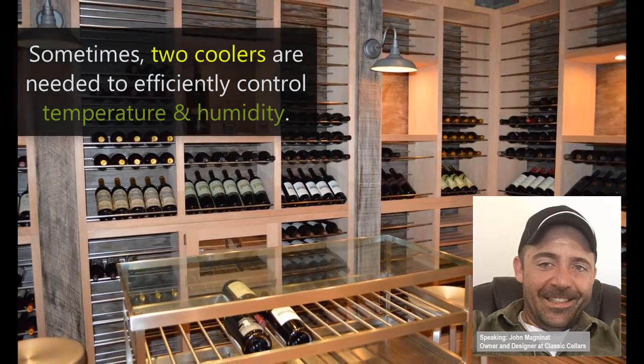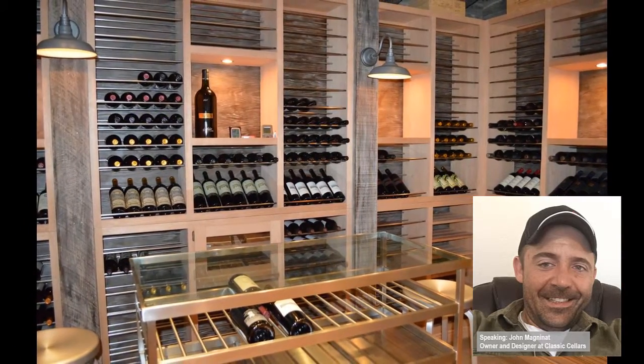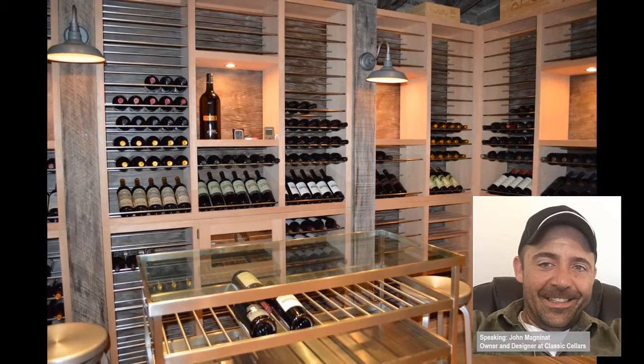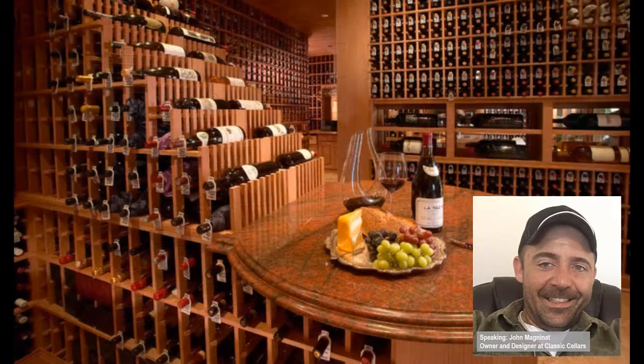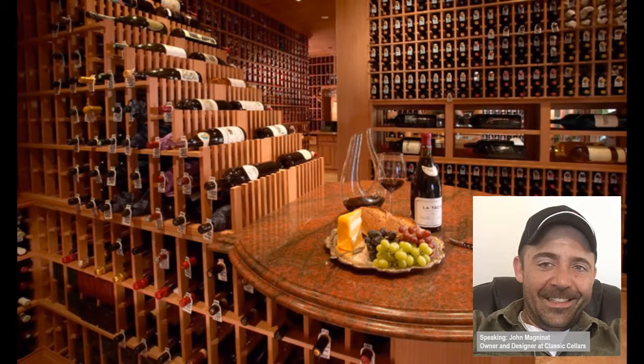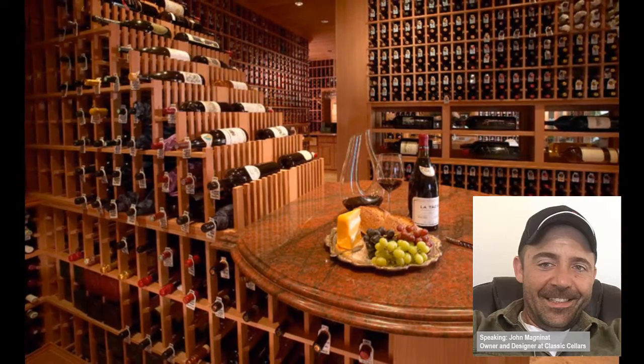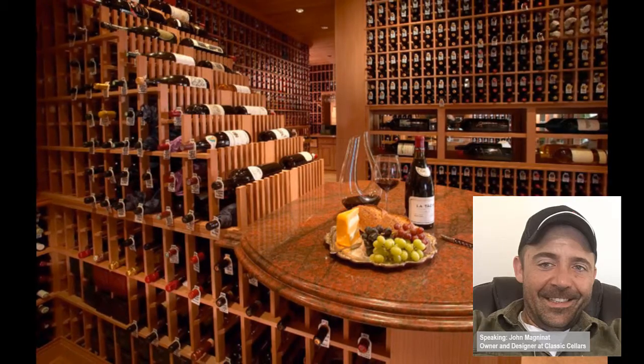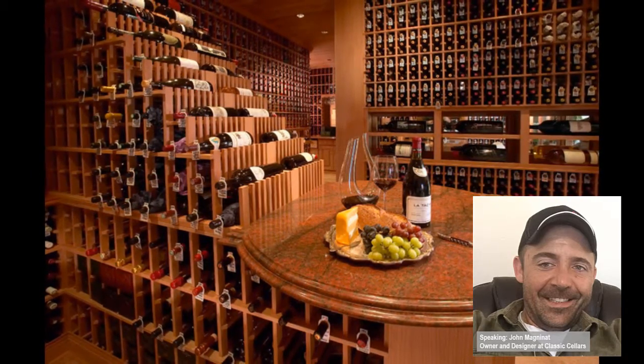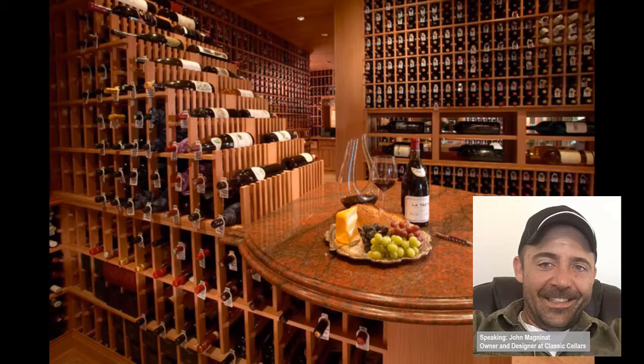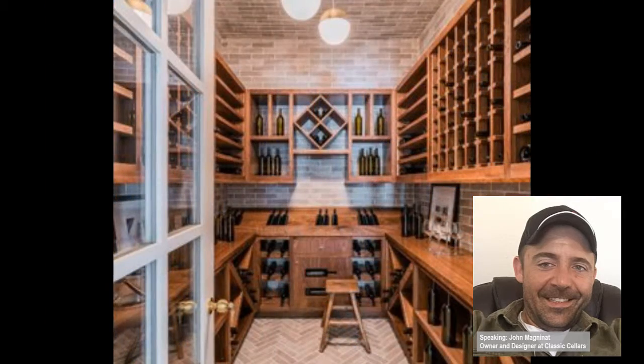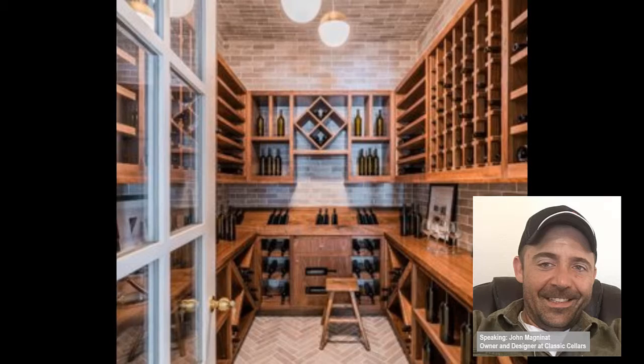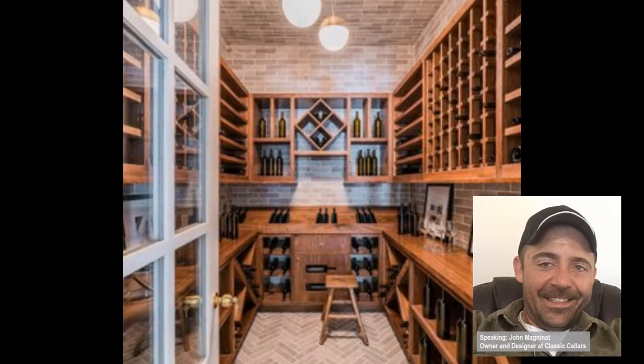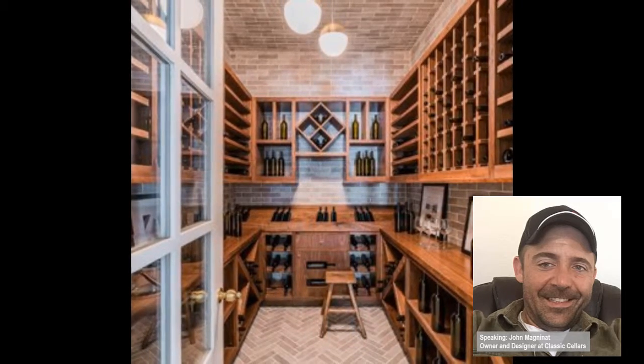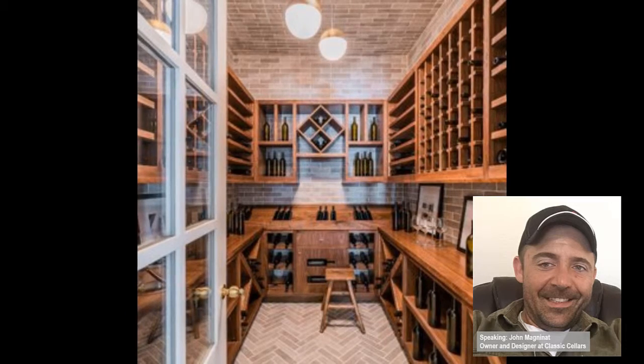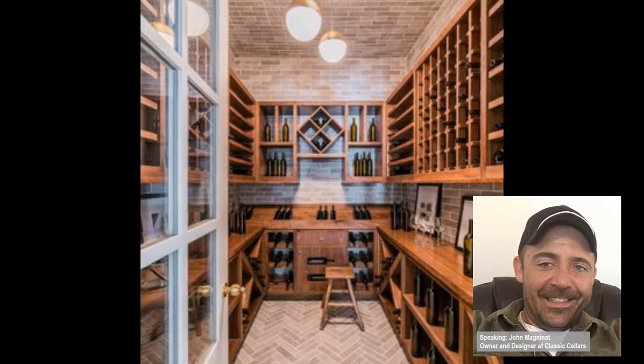So a split system with no ductwork is not going to work there. We ended up putting in a self-contained unit, and it needs to be sized to handle the load of both coolers, and now you get ductwork on both sides of the cooler. You get supply ductwork and return ductwork, so you run into some really challenging applications that people come up with that they want, and it all turns out neat. You just can't have one system to do everything. It does take all of them to be able to do it.